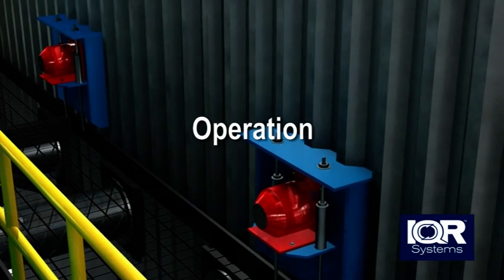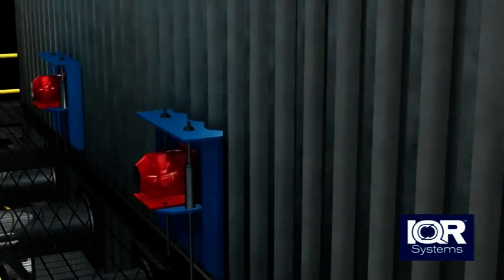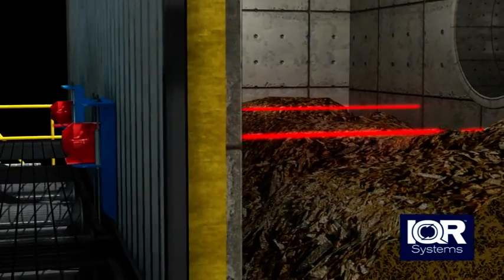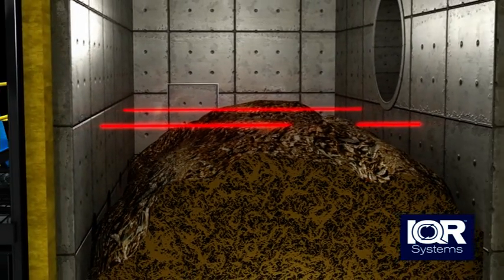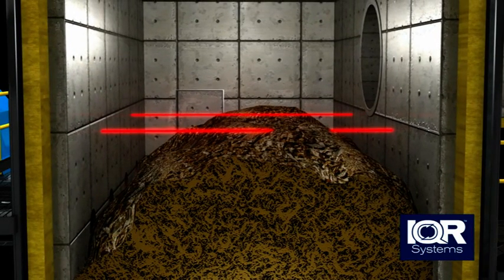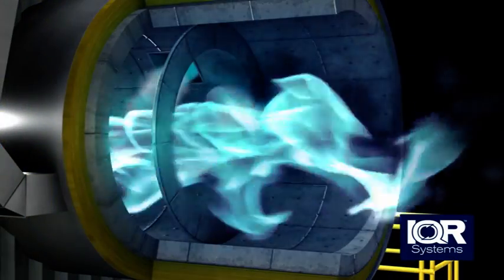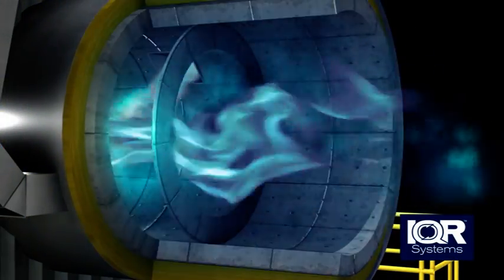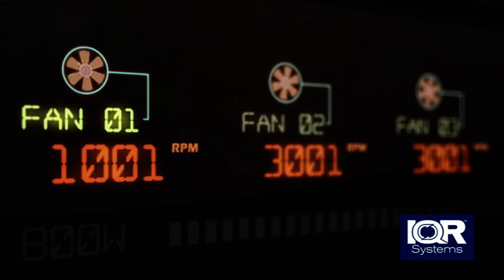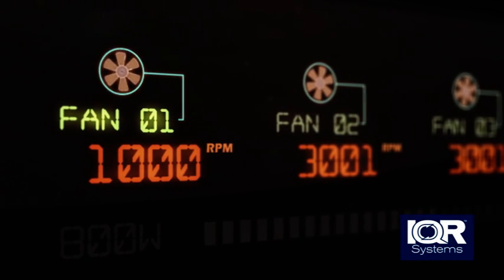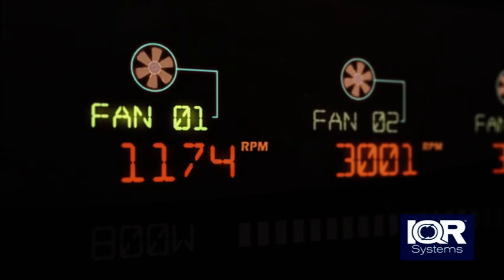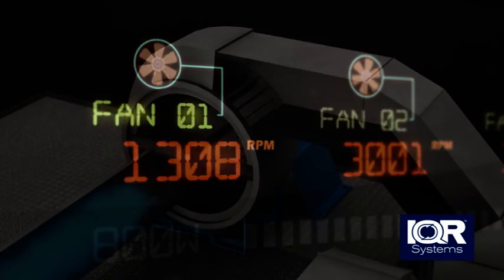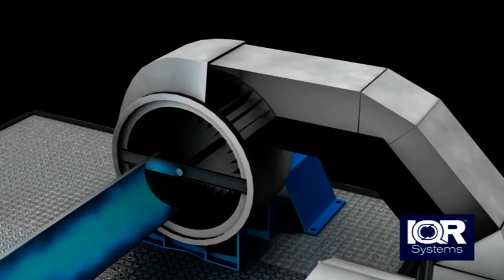It is of great importance that the fuel level in the gasifier is kept constant. This is adjusted using gamma level monitors. The system maintains a constant slow movement in the fuel bed, which is important for the process in order to keep a steady combustion in the flame. The energy output can quickly be regulated by adjusting the speed of the fans. A gasifier with a nominal effect of 10MW can be run at only 1MW with non-increasing emission.